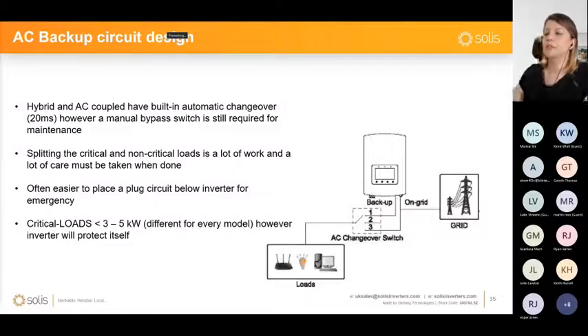So often, as I mentioned here, it's easier just to place a plug circuit below the inverter in case of emergency. That plug can be used if there is no grid. You can just plug in whatever load you have. Maybe you have a fridge that you want to be powered on during an AC outage, so you can just plug that fridge into that circuit in case the connection drops.